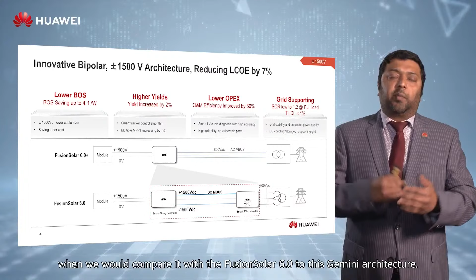As you might know, in the PV business, many power plants were built in the early days with 1100 volt old technologies. So round about 2013 to 2015, we were actually providing our solutions with this kind of voltage, 1100 volts, for power plant solutions. Then round about 2015, we moved into 1500 volt solutions for utility scale power plant projects. We would now take this 1500 volts, which is actually on the DC side, the low voltage directive. We would try to build on this to maximize the utilization of the DC low voltage directive by going into a bipolar architecture, which would be the plus-minus 1500 volt solution, our FusionSolar 8.0 Gemini solution.